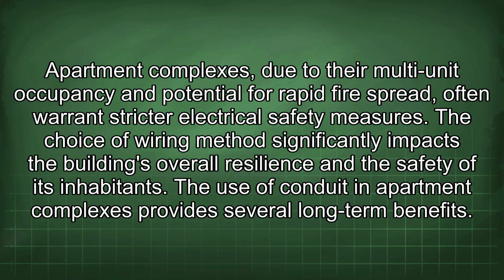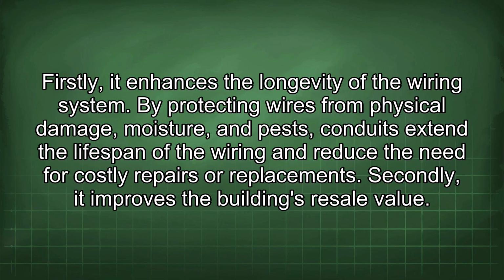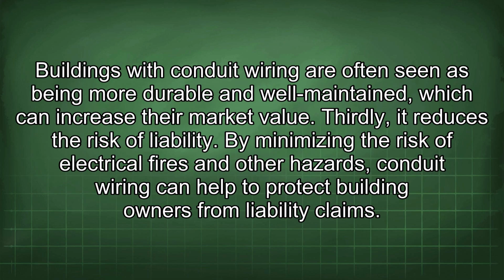The use of conduit in apartment complexes provides several long-term benefits. Firstly, it enhances the longevity of the wiring system. By protecting wires from physical damage, moisture, and pests, conduits extend the lifespan of the wiring and reduce the need for costly repairs or replacements. Secondly, it improves the building's resale value. Buildings with conduit wiring are often seen as being more durable and well-maintained, which can increase their market value.